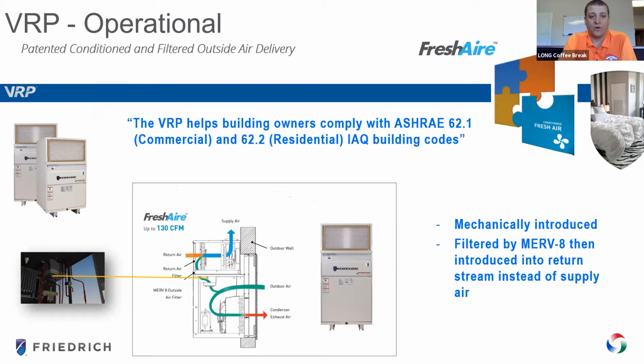And here's a general overview of the air path of the VRP unit. One thing I'd really like to take a minute to focus on is the ability to bring in outside air through the unit, condition it, and bring it to the space. By doing this, you're able to reduce the size of your central DOAS system. So maybe you're just providing outside air to your corridors and you're letting the VRP unit provide your outside air at the zone when you need it. And not have to provide extra DOAS, if it's an unoccupied room. So in the VRP unit, the outside air will circulate through the condenser coil and exhaust back out.